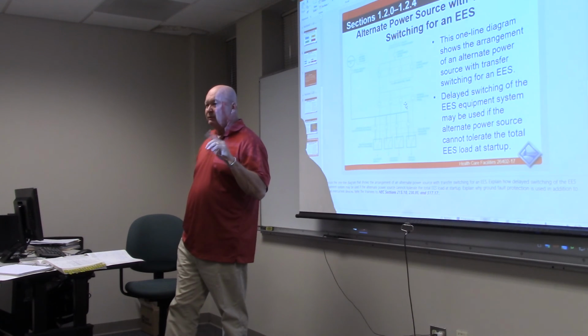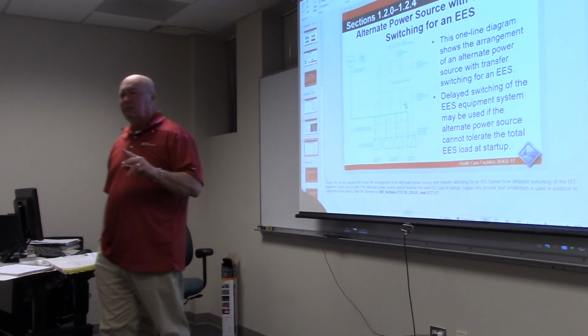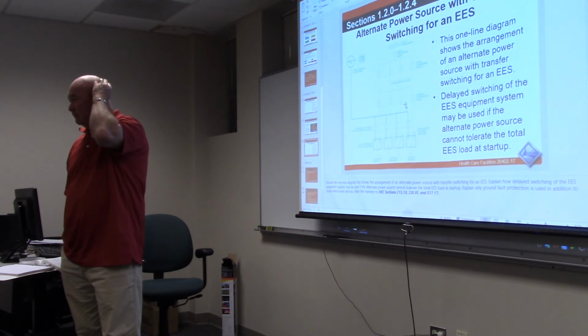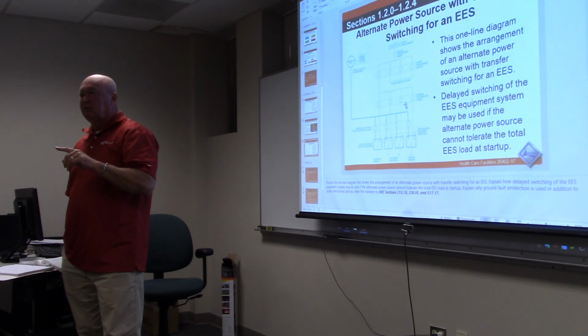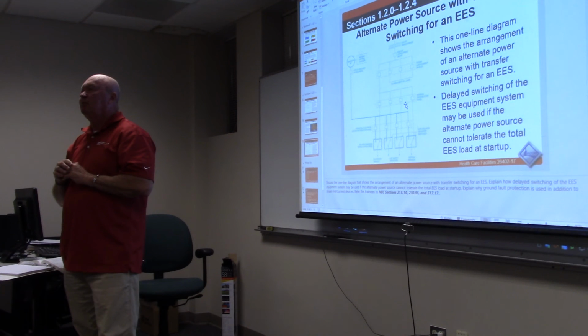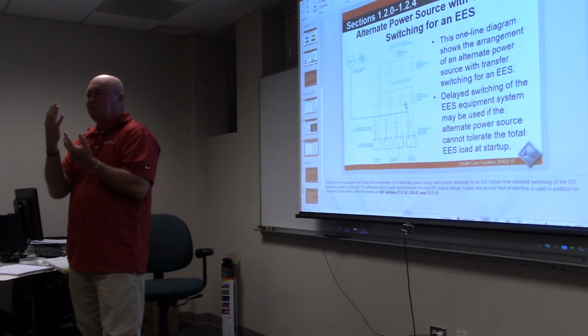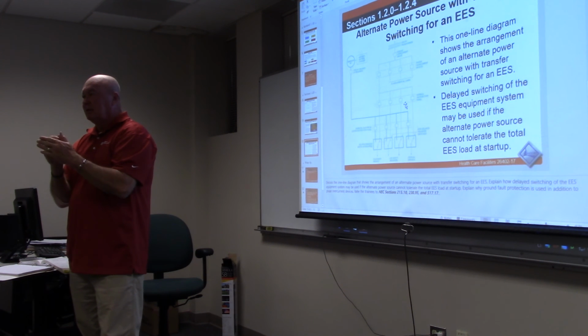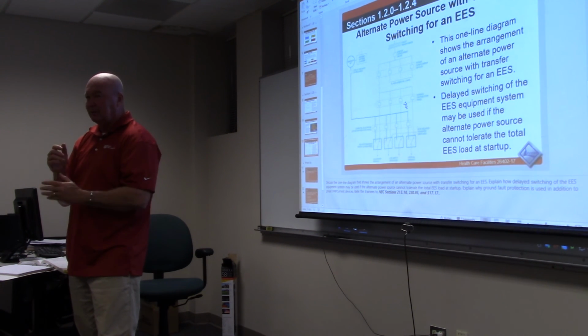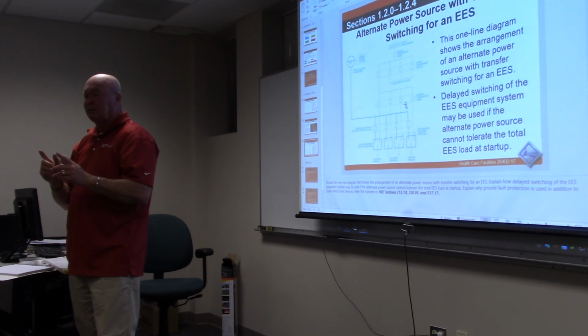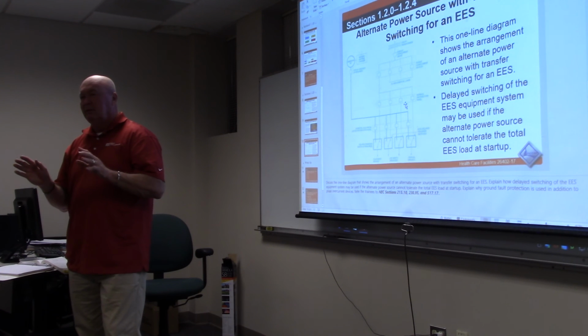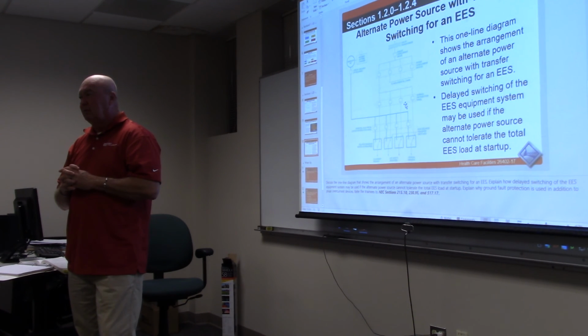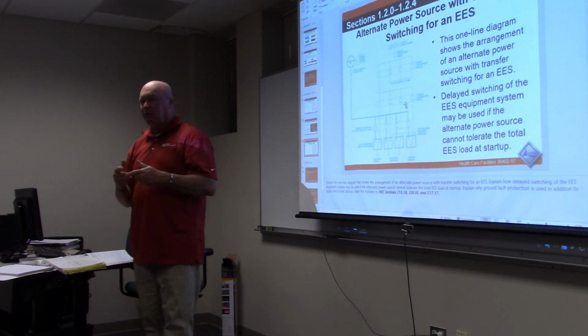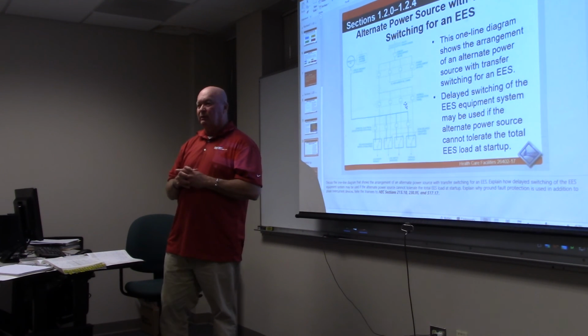The transfer switch, you may wire it, and you've got to be careful how this thing is connected. Matter of fact, we had a mistake on a job recently - I'm trying to remember the details, but the phasing was actually different from the top to the bottom. You would think it would be A, B, C on the bottom too, but it wasn't. Because of that, we were having issues in the building since we didn't check the phasing, and it wasn't marked appropriately from the generator people. We went on for months thinking it was something other than what it was, until we figured out the rotation was wrong because the phasing was wrong.